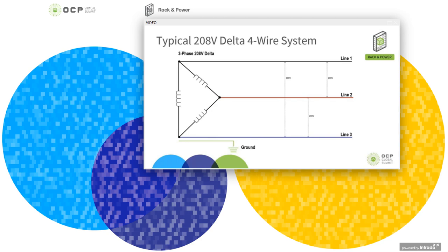So what happens here, this is known as a three-pole four-wire system, or a three-pole plus protective, where the single-phase power is consumed by sourcing from each of two phases. So you have a line one to two, a line two to three, and a line three to one. We get single-phase feeds at 208 volts. This is typical of the United States, also much of North America, some of South America, and Japan uses a similar system, only the voltage is 200 instead of 208.